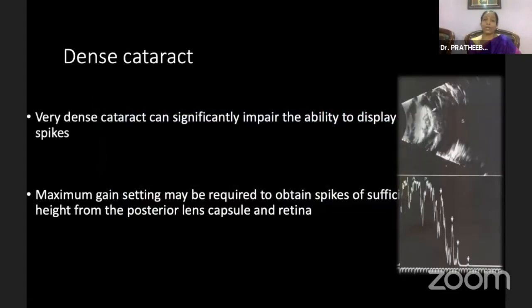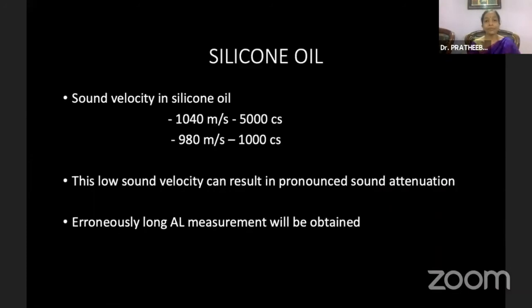When dealing with a very dense cataract, sound waves may have difficulty penetrating, resulting in poor quality spikes — increase the gain settings. When dealing with a silicon oil-filled eye, the mode must be changed to silicon oil mode because sound waves travel slower in silicon oil. This can cause pronounced sound attenuation and erroneously give a falsely long axial length, affecting IOL power calculation.